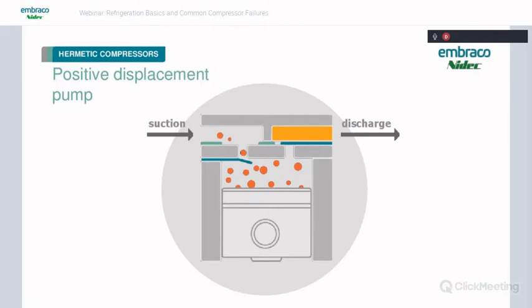So a little bit about that positive displacement pump. Basically, you have a piston and a cylinder, and it's just like a piston and cylinder inside a car. It's going to draw in suction gas on the downstroke, provide compression on the upstroke, and then the discharge valves are going to deflect to provide compression. It's a positive displacement pump, and what this means is anything that this pump pulls in is going to try to compress. This is the reason we never want to introduce any liquid refrigerant into the cylinder or the valves, because liquids do not readily compress.